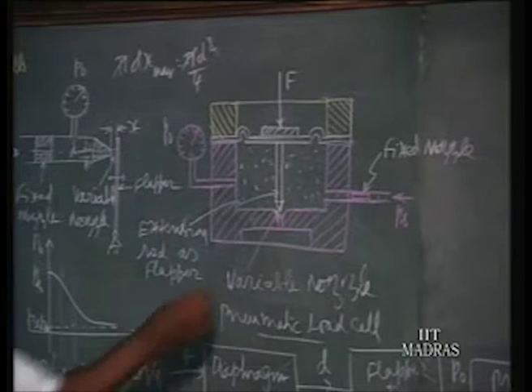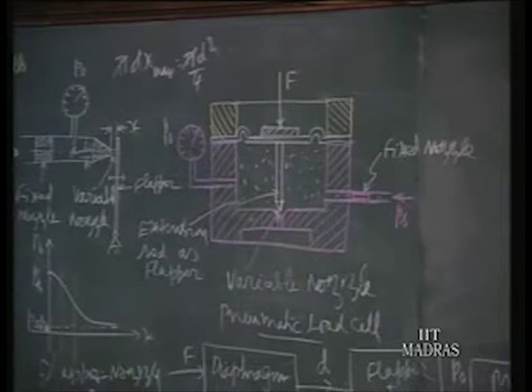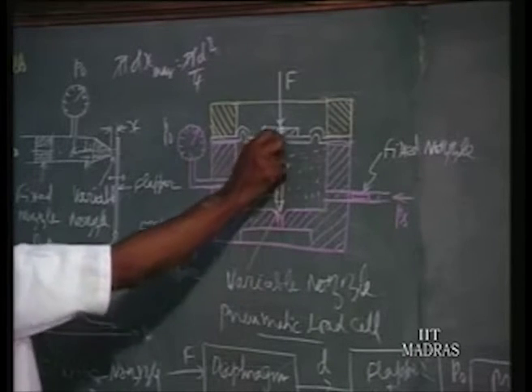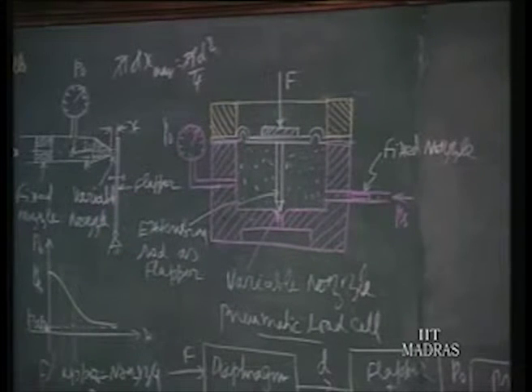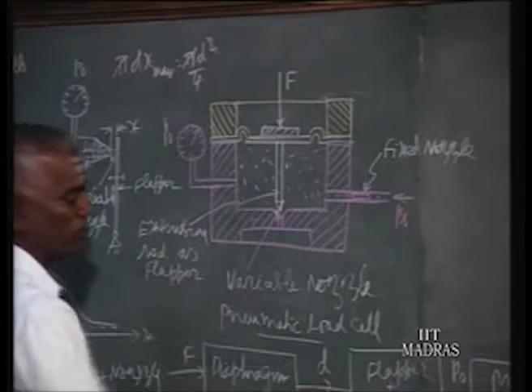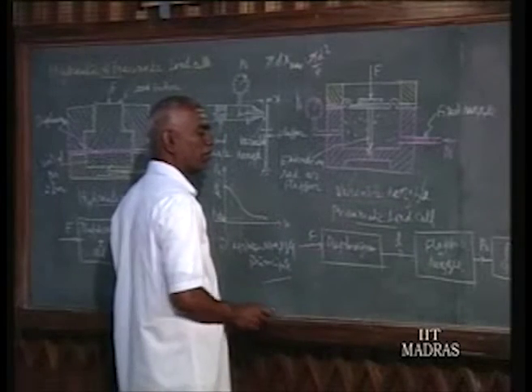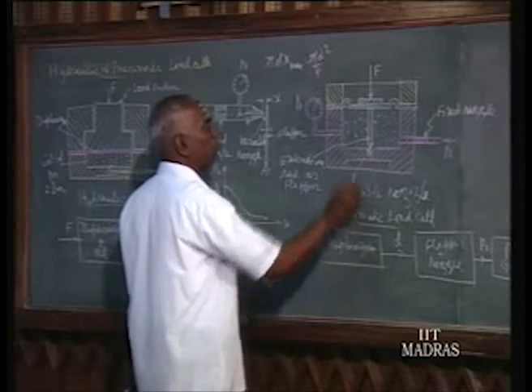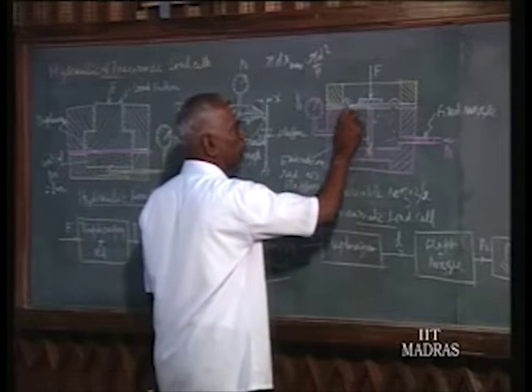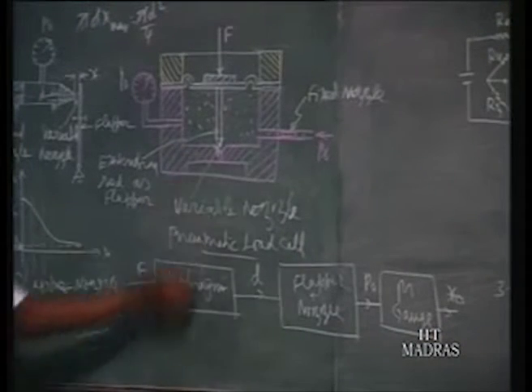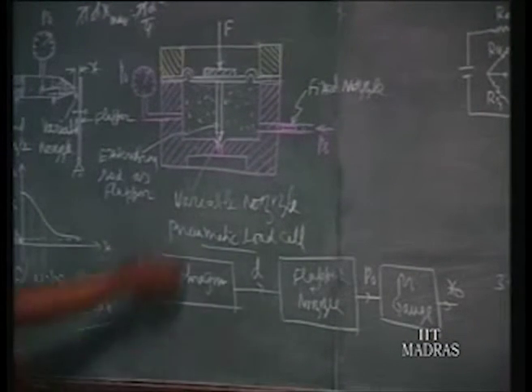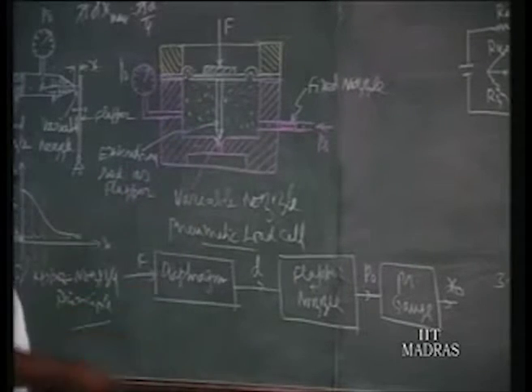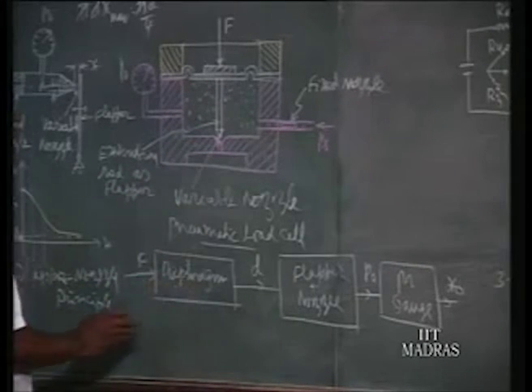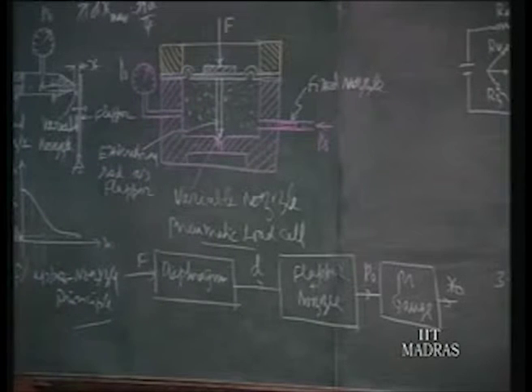So such a distance is given to this extension rod by the diaphragm when the diaphragm is acted upon by a force F. See this block diagram or signal flow diagram: force is given to the diaphragm, then the diaphragm gets deformed. This deformation is carried to this nozzle opening by this extension rod. So the amount of opening is varied when the diaphragm deforms. That is our variable area, analogous to a variable nozzle.